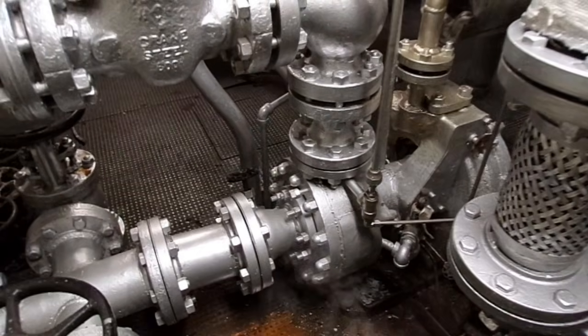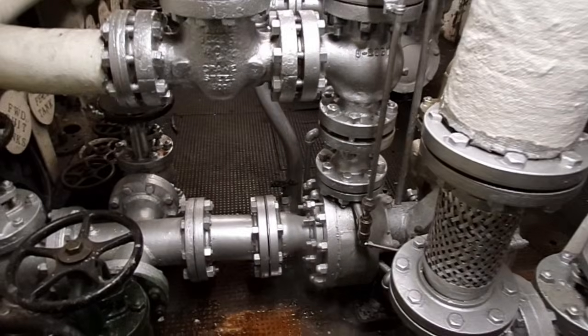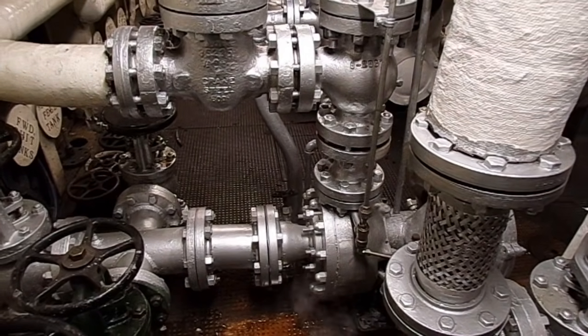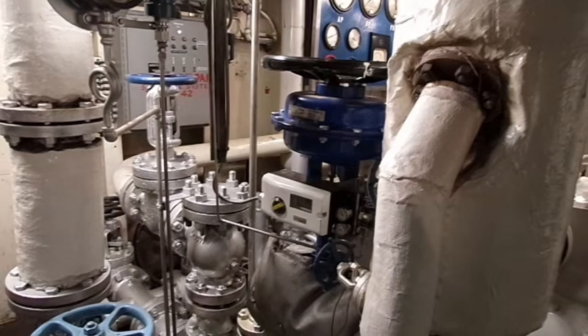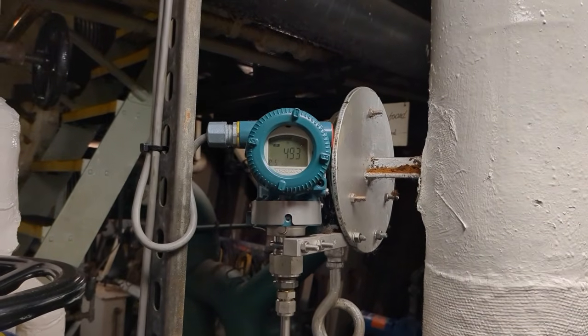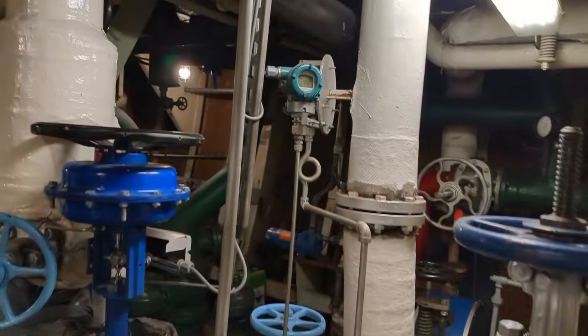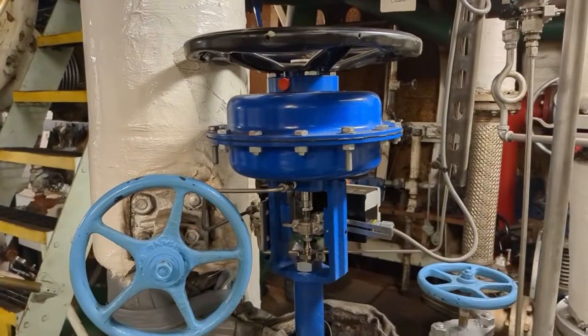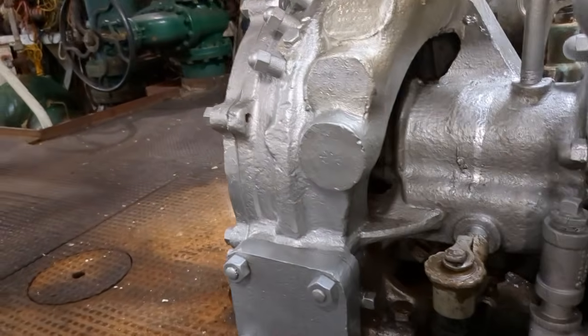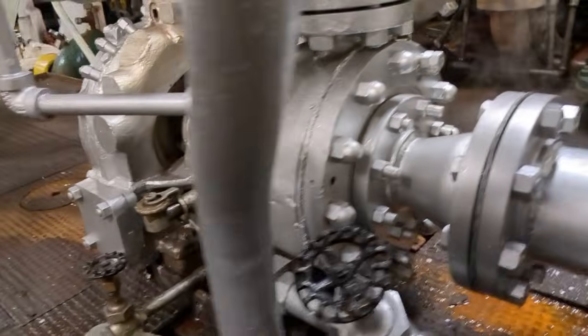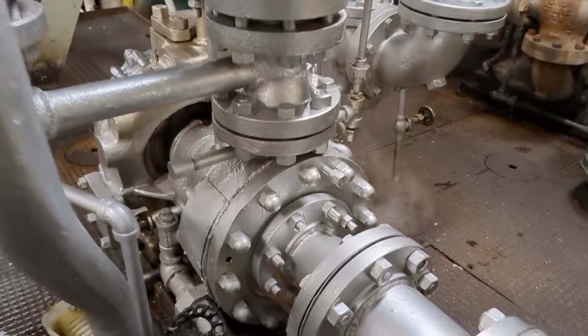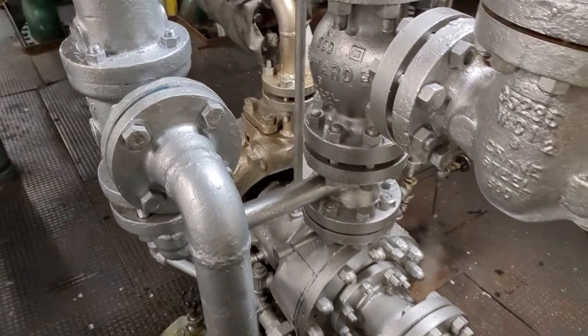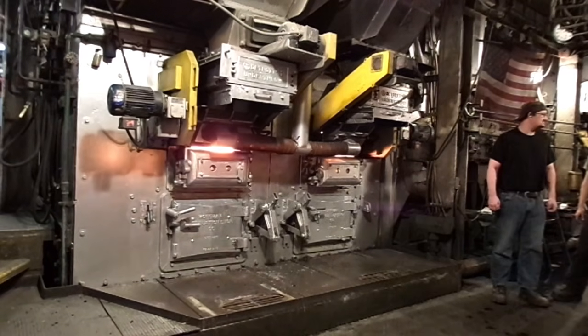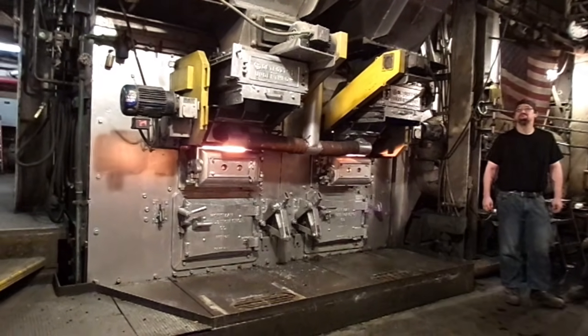It has a single centrifugal impeller driven by a steam turbine that can reach speeds of about 9,000 RPM. This turbine is throttled based on water pressure. Right now, water pressure is set to 490 psi. The feed water pump turbine also exhausts into the deaerator. The boilers will turn this water into high pressure steam that powers everything from the propellers to the lights. We will explore the boiler room in the next video.